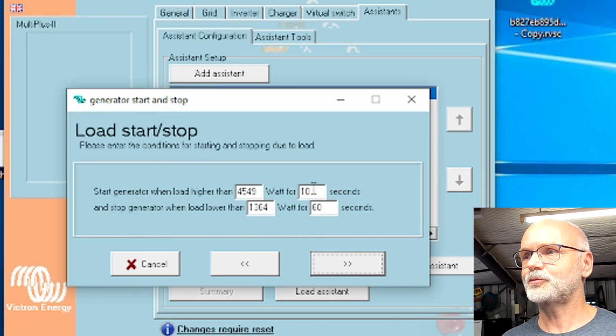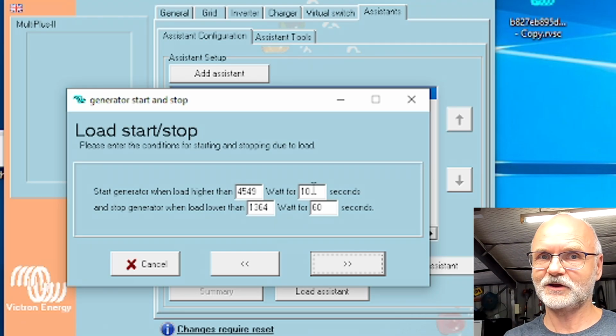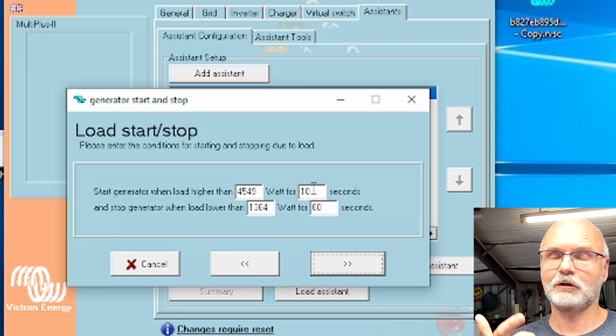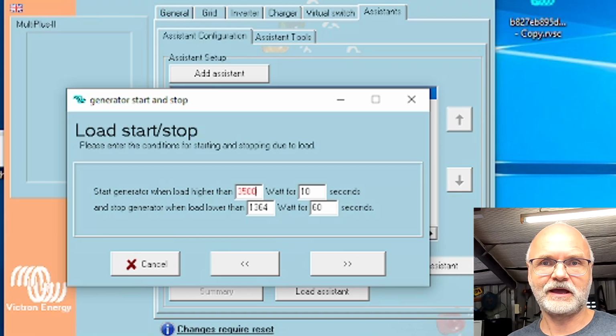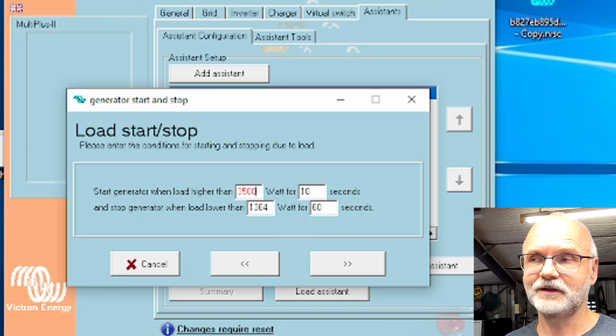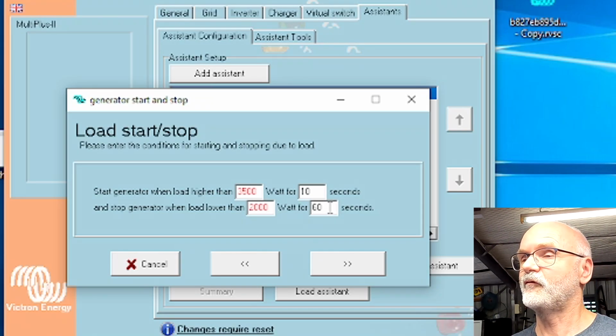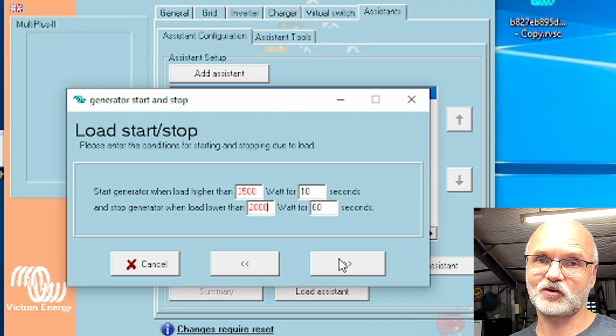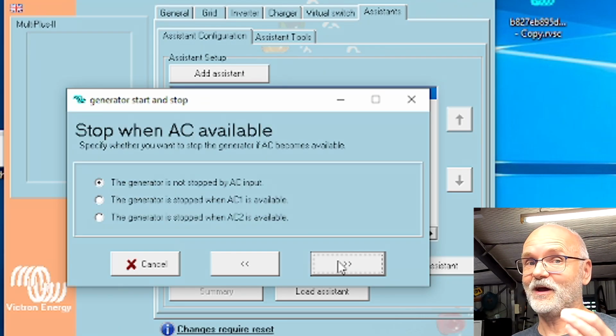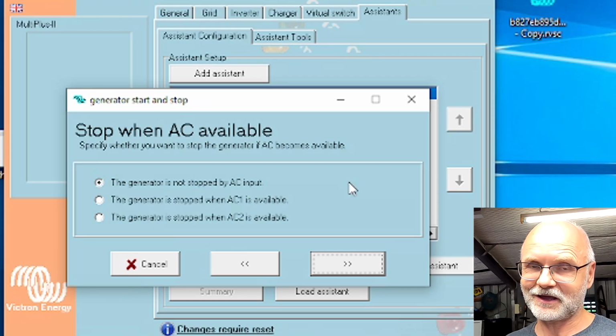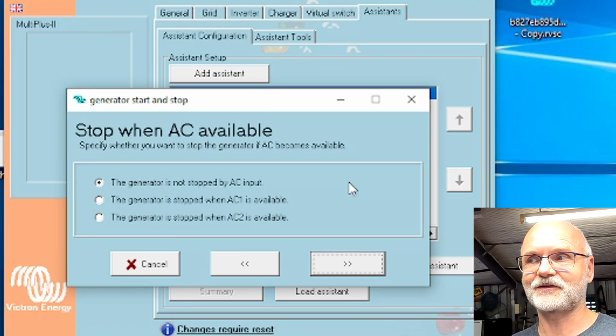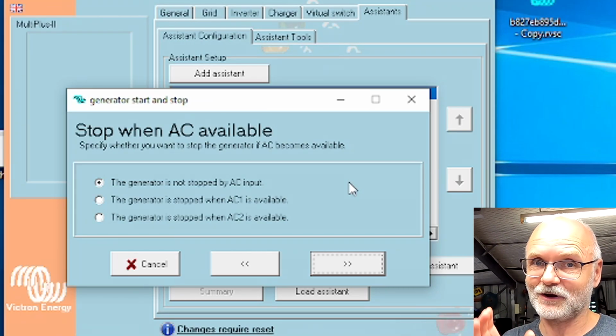And here we can now program the start threshold and the stop threshold for our Multiplus. Again, we can say if the load output is more than 2500 watts for 10 seconds, start the Phoenix. If it goes below 2000 watts for 60 seconds, stop the Phoenix. And this is a very important feature. In our case, the shore power comes from the Phoenix. The Phoenix is also our generator.